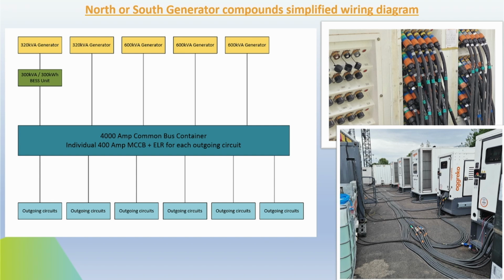From a protection point of view, although it's technically not a requirement in BS 7671, for the most part, all mains distribution circuits are protected by earth leakage relays or residual current monitors to provide that sort of additional protection, if you like, because as you can see, a lot of the cables are running on the floor, but generally those are only in controlled areas.